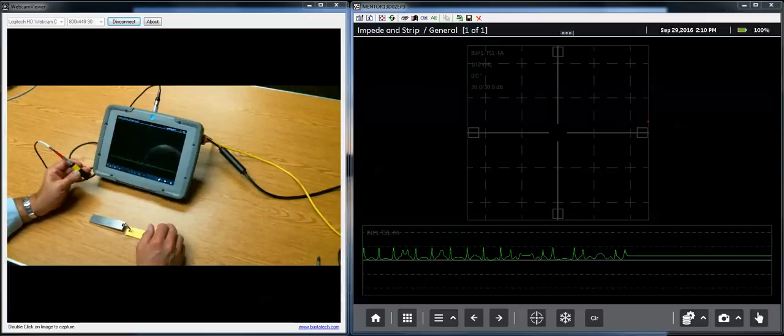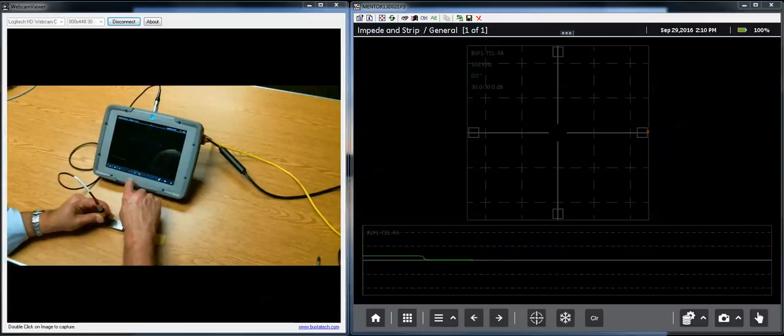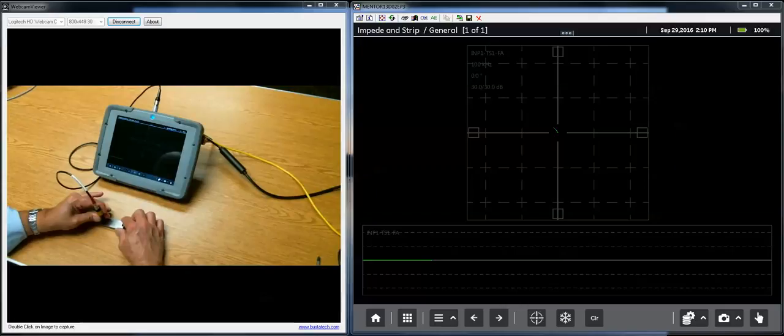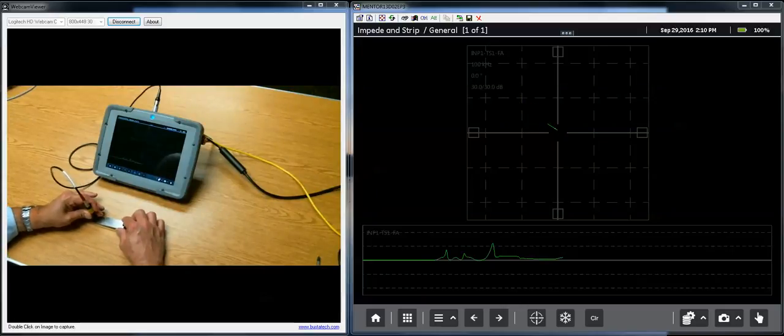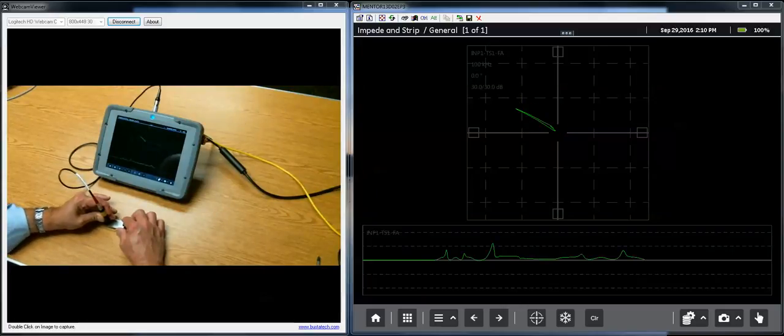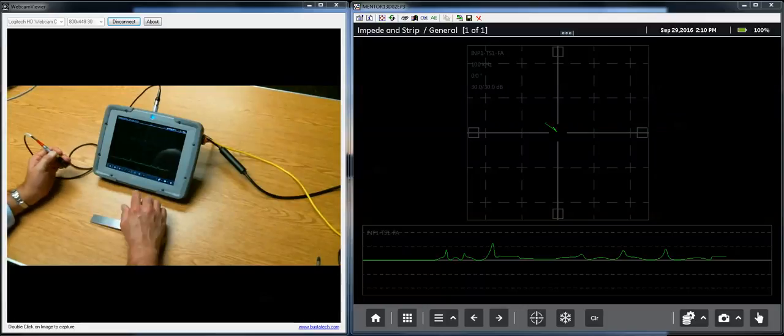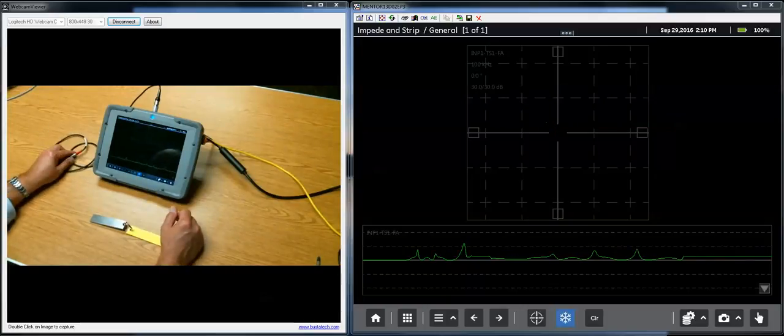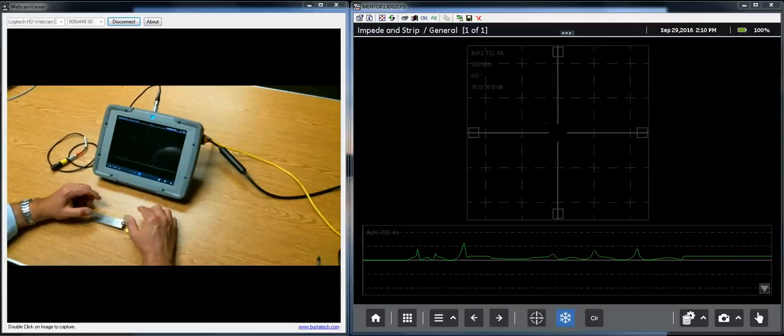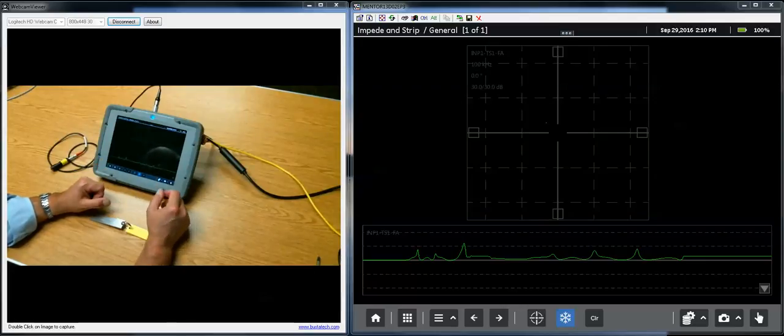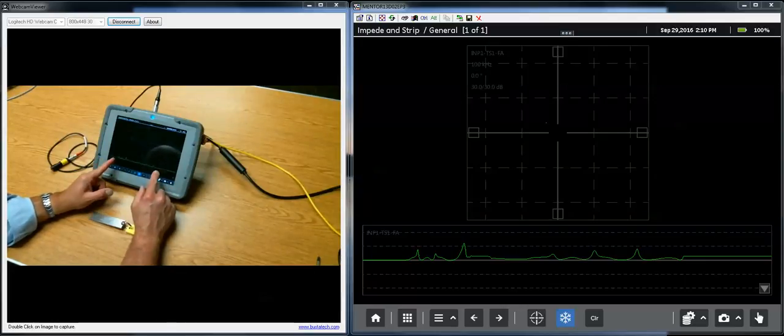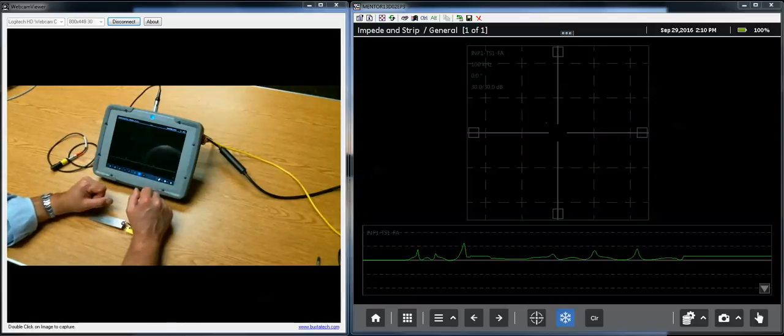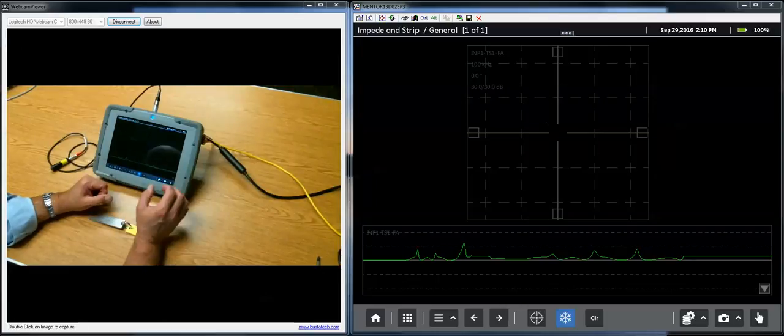So let's go back. We'll clear our signal, put our probe down on the standard, we'll balance, run across a series of notches. There's a half millimeter, one millimeter, two millimeter notches, and we'll freeze. Now once we've acquired signal and frozen, we have a number of options that we can use to play back parts of that signal that interest us and further make adjustments to the instrument.